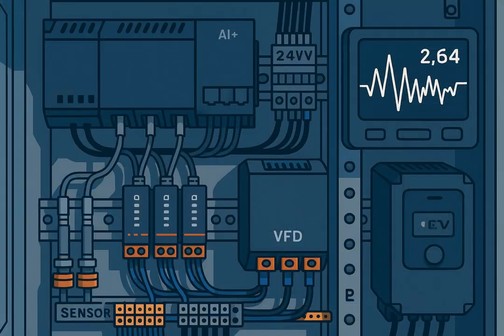In many real industrial panels, the problem comes from one very simple mistake. The sensor ground is connected to the PE bar instead of the PLC analog ground / AGND. In this video, we'll explain why grounding is so critical for analog signals, what happens when you connect sensor GND to PE, and the correct wiring method to get a clean, stable measurement.